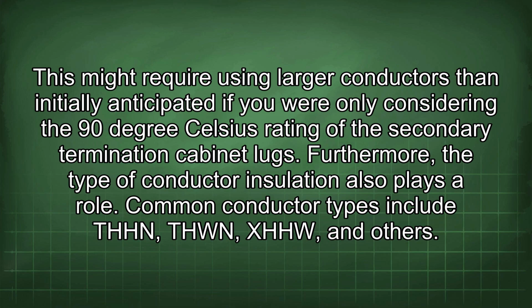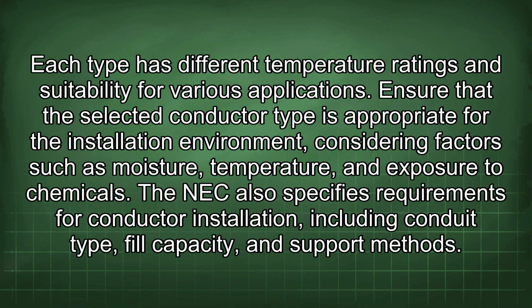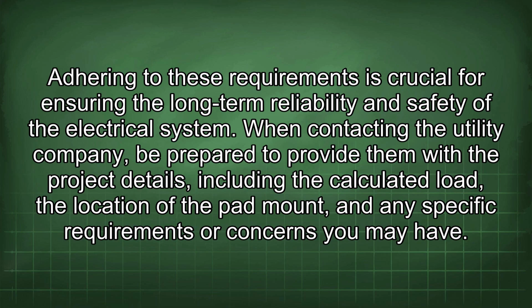secondary termination cabinet lugs. Furthermore, the type of conductor insulation also plays a role. Common conductor types include THHN, THWN, XHHW, and others. Each type has different temperature ratings and suitability for various applications. Ensure that the selected conductor type is appropriate for the installation environment, considering factors such as moisture, temperature, and exposure to chemicals. The NEC also specifies requirements for conductor installation, including conduit type, fill capacity, and support methods. Adhering to these requirements is crucial for ensuring the long-term reliability and safety of the electrical system.